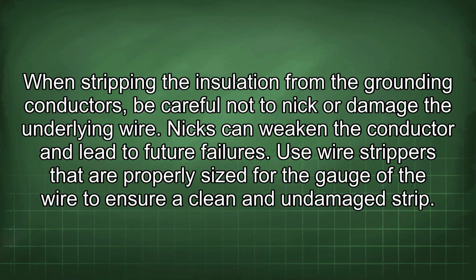When stripping the insulation from the grounding conductors, be careful not to nick or damage the underlying wire. Nicks can weaken the conductor and lead to future failures. Use wire strippers that are properly sized for the gauge of the wire to ensure a clean and undamaged strip.